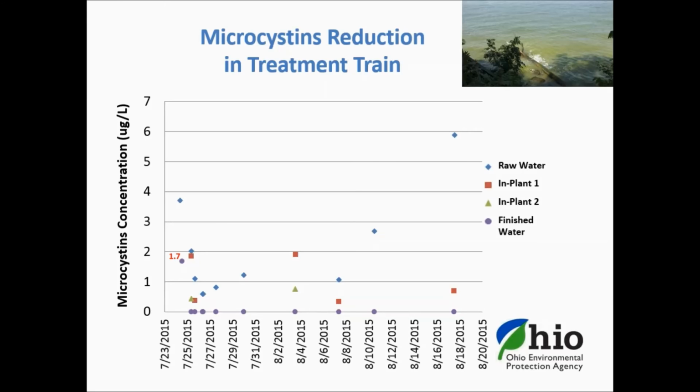The result was worth it. Microcystins were not detected in repeat samples, and an advisory was not issued. The public water system is also lucky in that source concentrations decreased after the initial detection. But at the last sampling point in this graph, you can see that when source concentrations increased again, the optimized plant was able to effectively eliminate the microcystins and have no further finished water detections.